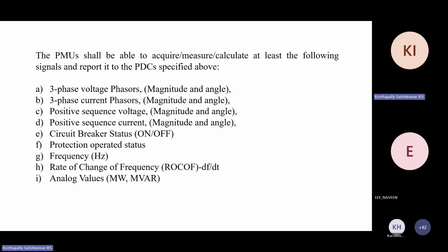So these are the requirements. The PMU shall be able to acquire, measure, and calculate at least the following signals, because as I told, each PMU can give you hundreds of data, but we told them at least these should be given, like A to I. Each PMU output should give at least these things, and above this, if the PMU gives more data, that's well and good, but this is the minimum requirement. Three-phase voltage phasors, as I told earlier, magnitude and angle, three-phase current phasors, positive sequence voltages, positive sequence currents, circuit breaker status, protection operated status, frequency, rate of change of frequency, and analog values. So these are the outputs of the PMU. And as I explained in the initial slides, the inputs to the PMU are the CT and PT inputs from the substation, and the GPS signal.